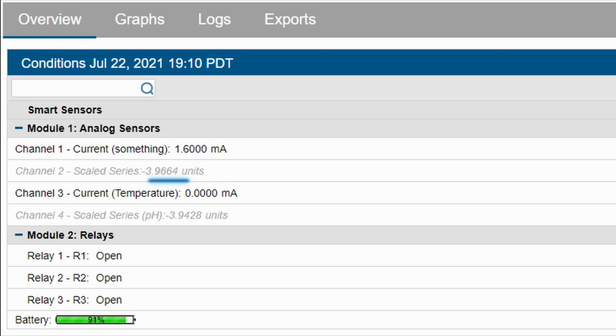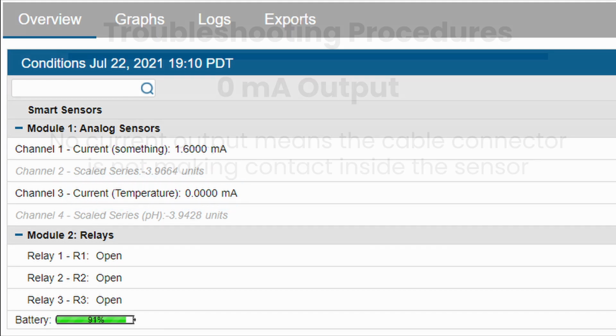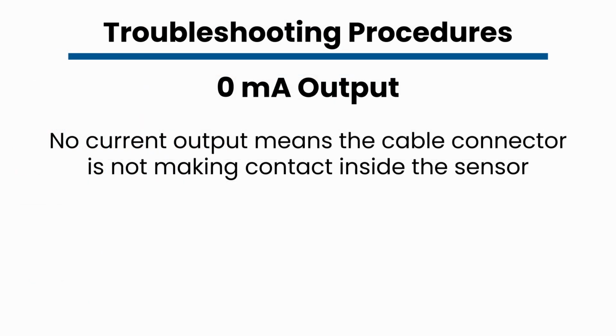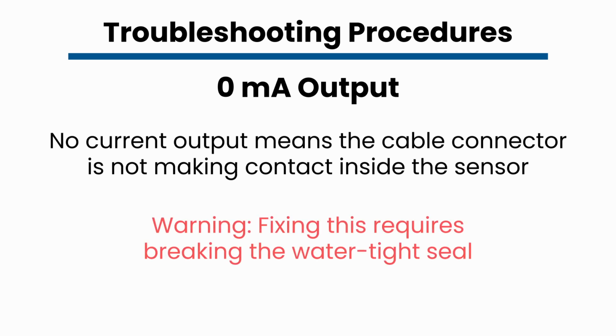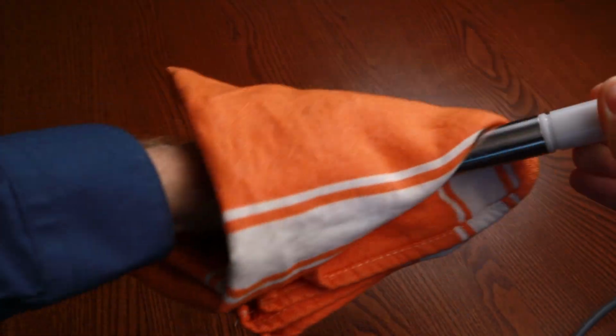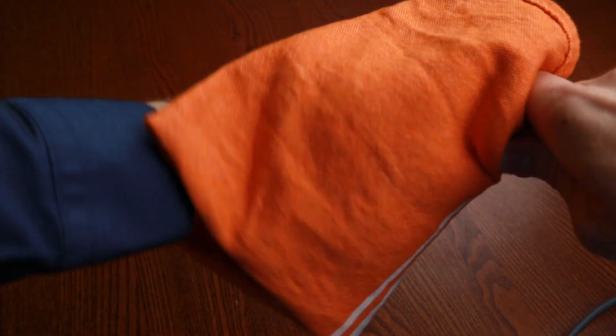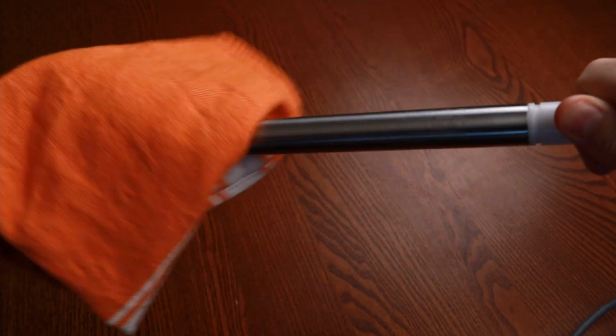Start by checking the current output of the temperature wires. If there is no output, then the cable connector is likely not making contact. As mentioned in the precautions, checking the connection requires breaking the watertight seals. Always wipe down the sensor thoroughly to prevent water from entering the housing. Even a small amount of trapped water can cause corrosion over time.